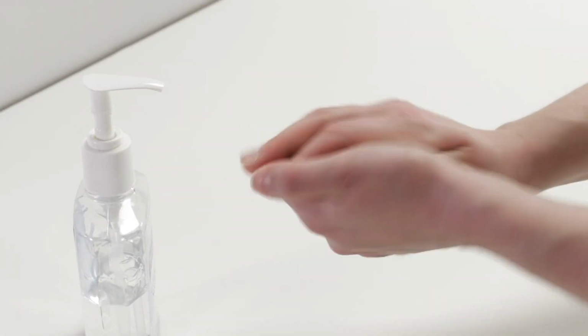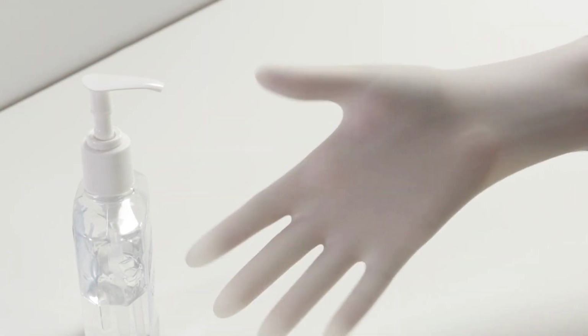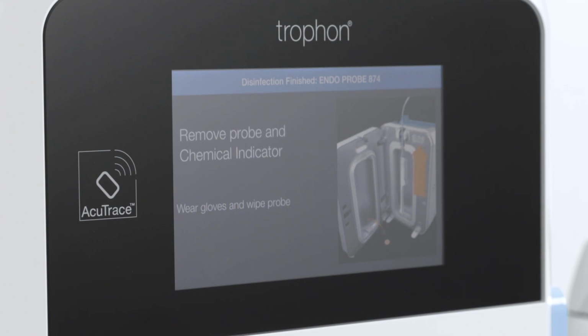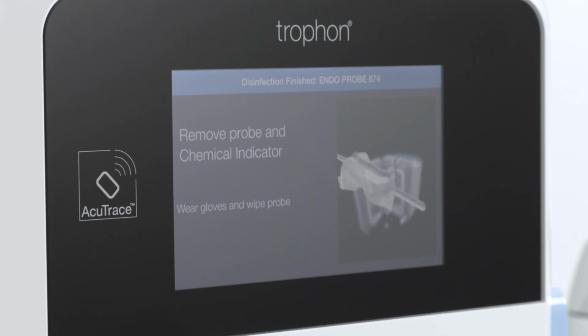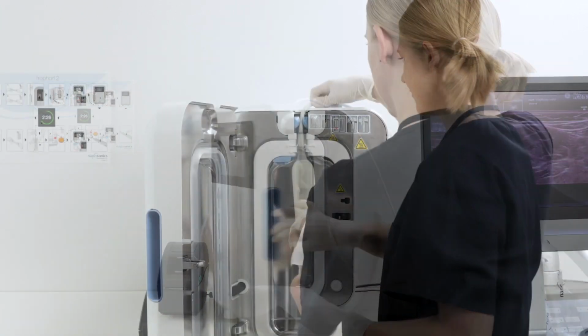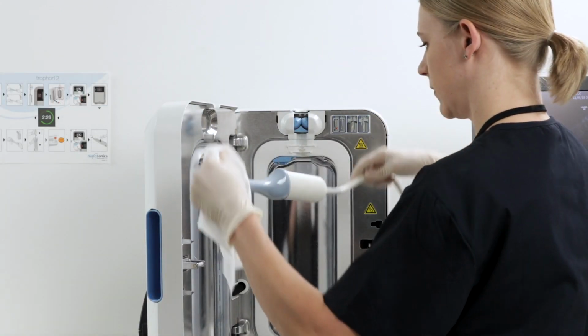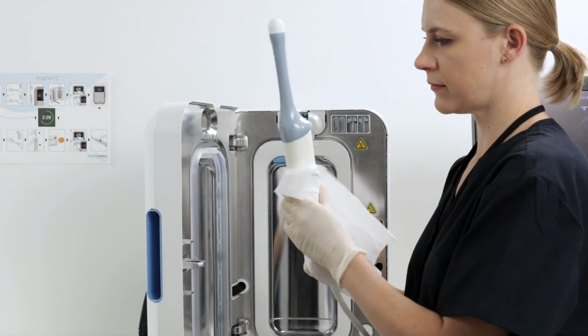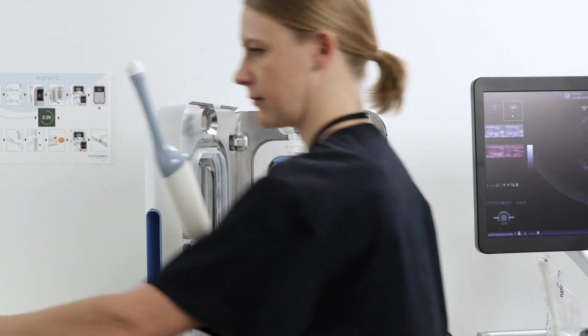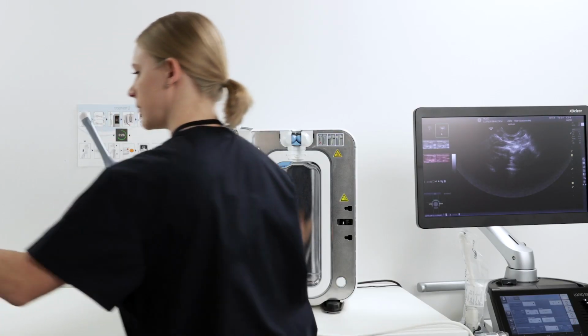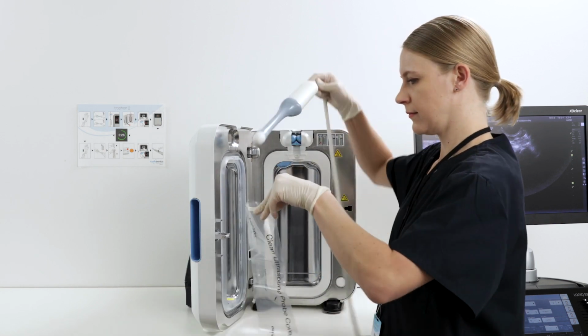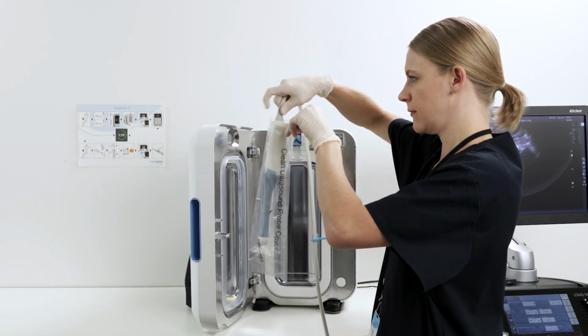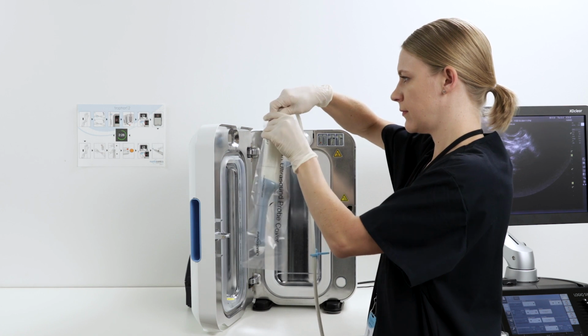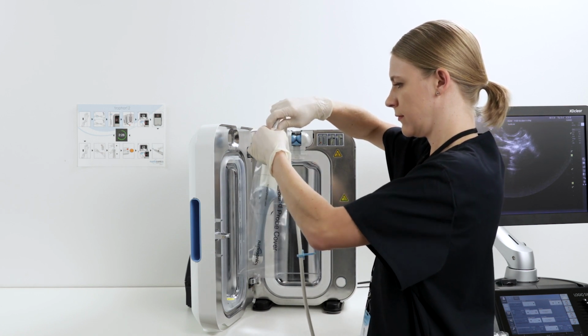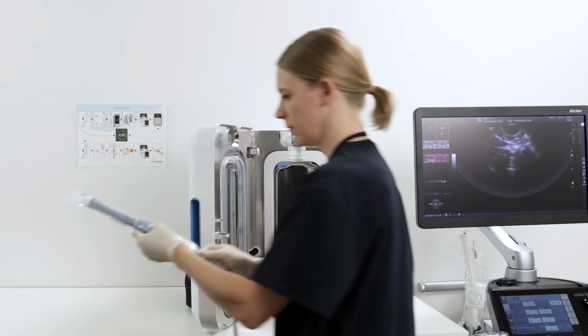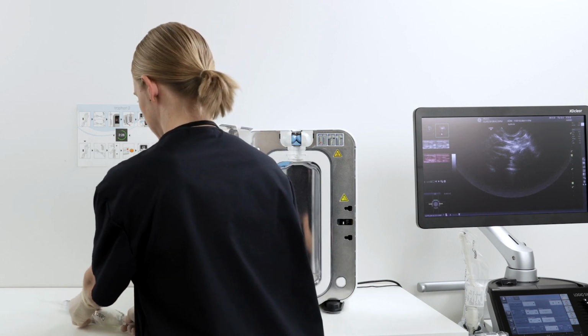Perform hand hygiene and put on a fresh set of gloves. The screen will prompt you to remove the probe and chemical indicator. Open the chamber door to remove the probe. Lightly wipe the probe with a trophon companion drying wipe. Store the probe using a trophon clean ultrasound probe cover. Insert the probe into the probe cover and wrap the securing tie around the cable strain relief. Then place the covered probe in a designated clean area on the bench or console holder.